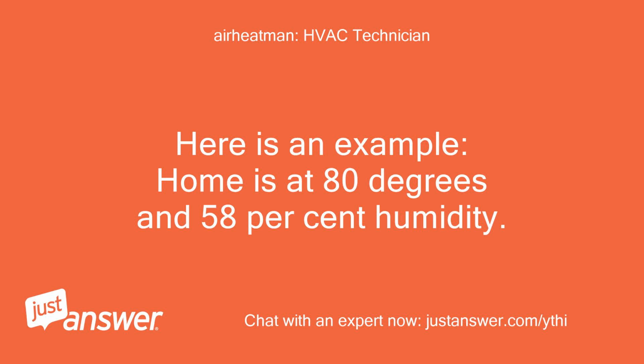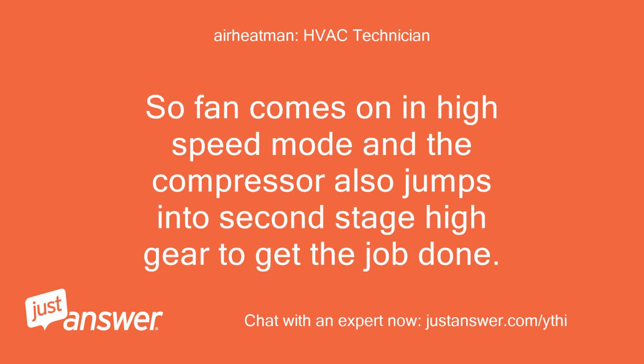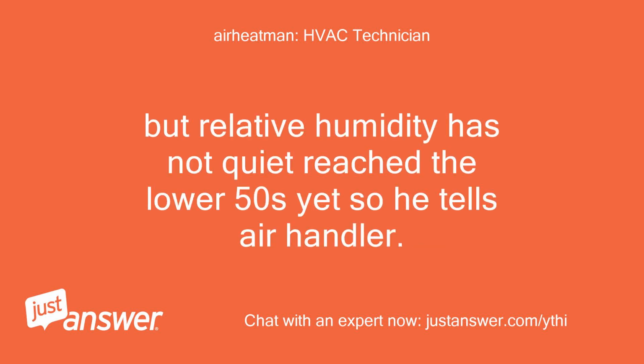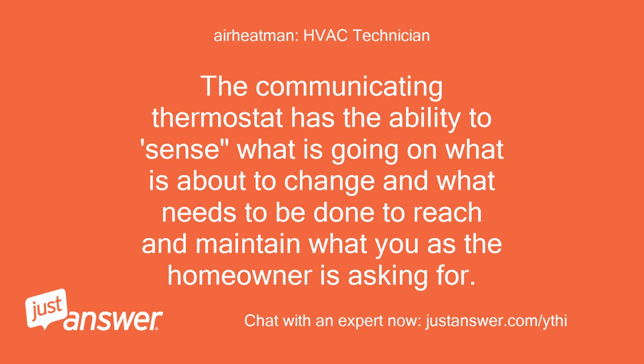Here is an example: home is at 80 degrees and 58% humidity. You set it to 73 and 51%. The thermostat senses that and says, okay guys, to the air handler and condenser, we have to get busy here. So the fan comes on in high speed mode and the compressor also jumps into second stage high gear to get the job done. After some time, as the temp drops to say 75, the thermostat senses we are getting close, so he tells the outdoor condenser, hey bud, you can back off to first stage now as we are approaching the target set point. But relative humidity has not quite reached the lower 50s yet, so he tells the air handler that the condenser is going to back off, but we need you to adjust the airflow just a few hundred RPMs and let's get this humidity in check too. In other words, the communicating thermostat has the ability to sense what is going on, what is about to change, and what needs to be done to reach and maintain what you as the homeowner are asking for.